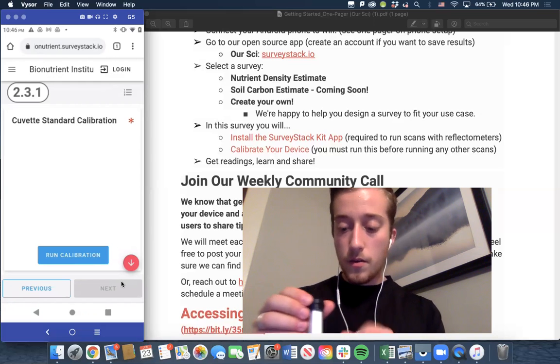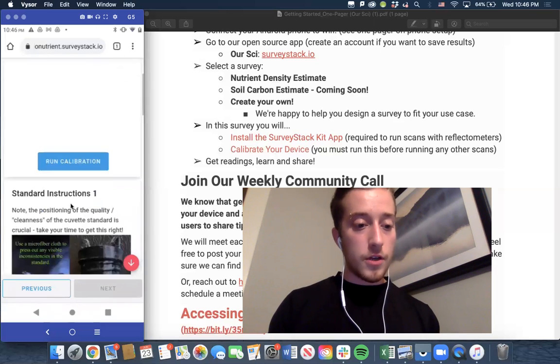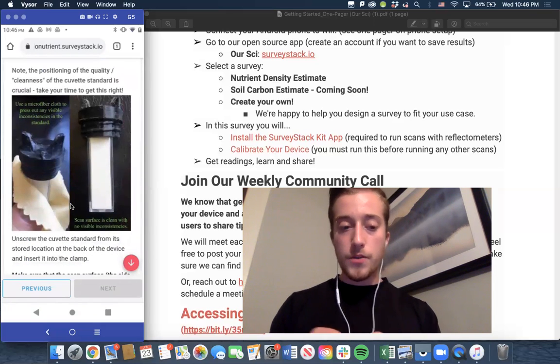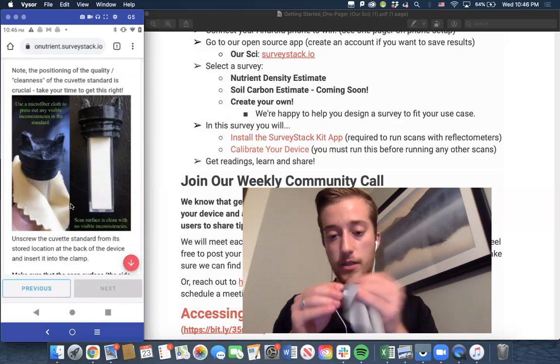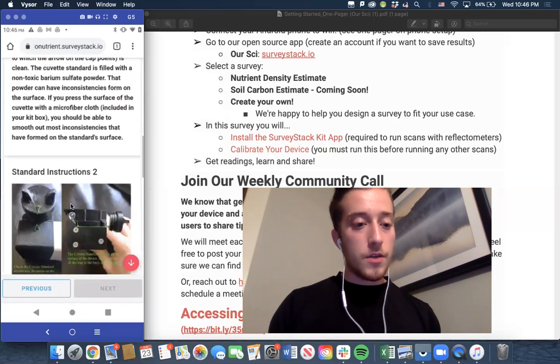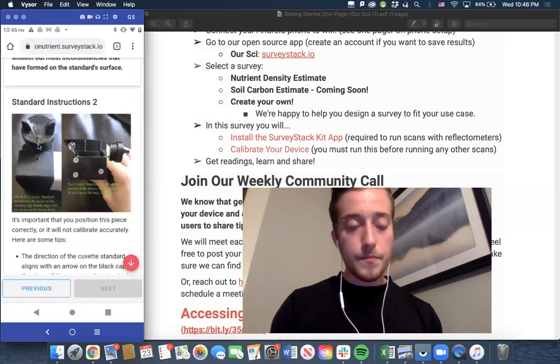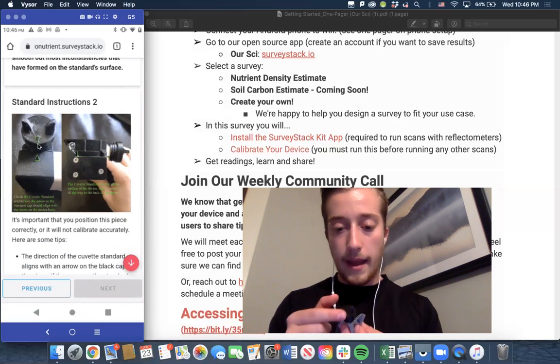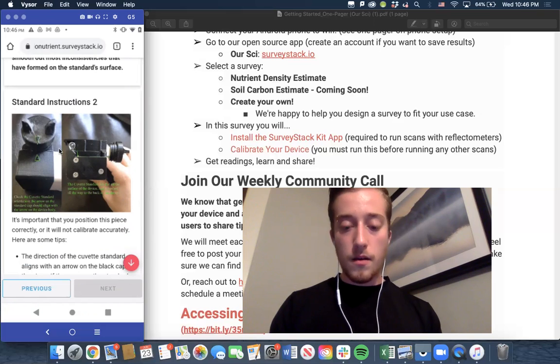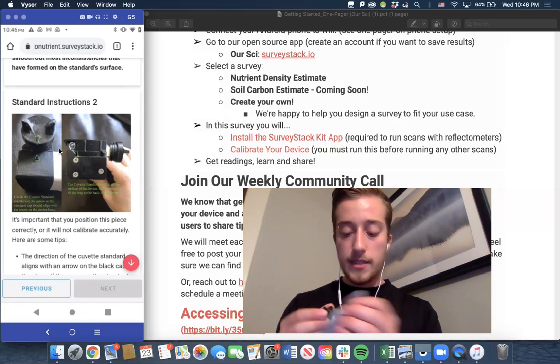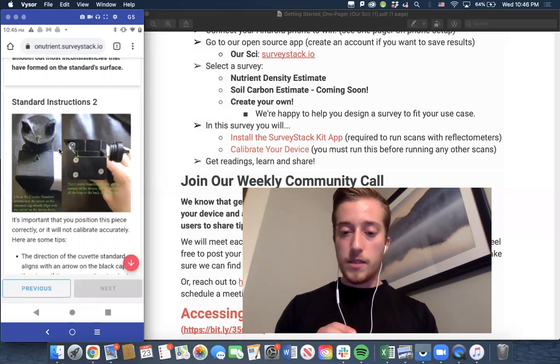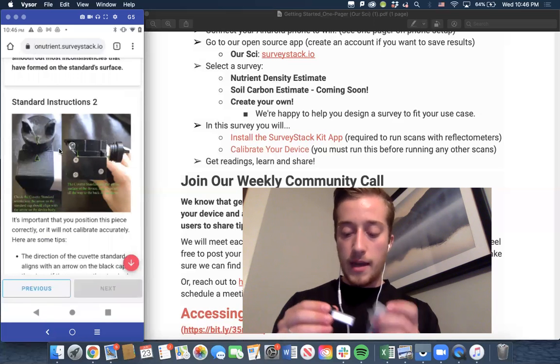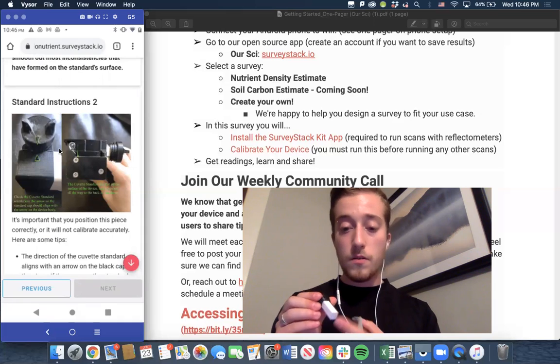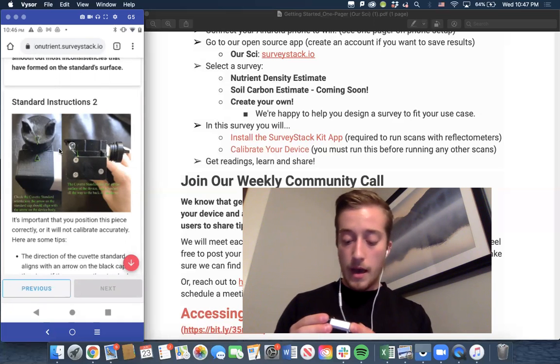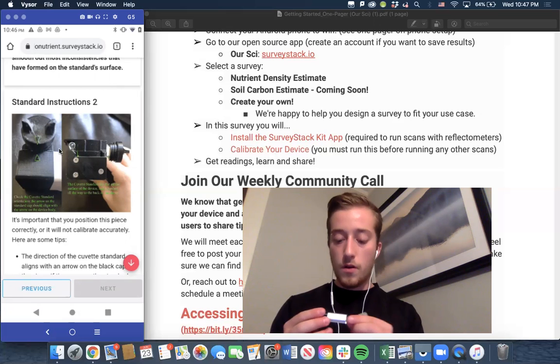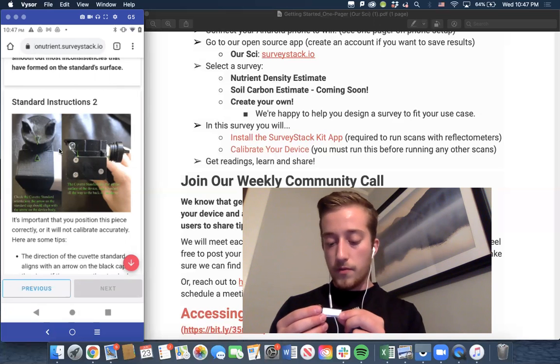When you get this, looking at the instructions, you want to make sure that it's clean. So you can use your microfiber cloth and just clean it off. As a note, you should look for an arrow and know that the face to which the arrow points is the one that matters. So you want that face to be as clean as possible. There shouldn't be any residue on the outside of the cuvette. And also this is packed with a barium sulfate powder. And that powder can get sort of clumpy over time if you don't use it or if the device is in motion a lot.